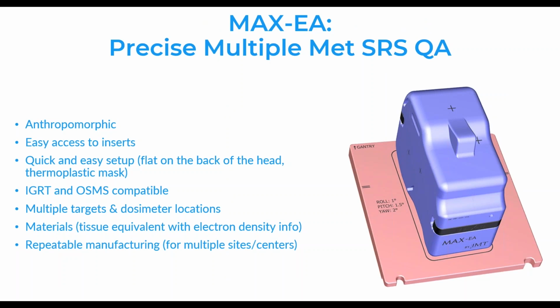So in summary, the Max EA can be used for a precise multiple Met SRS QA. It is anthropomorphic. With the cover, it's very easy to access the insert, and you could quickly set it up because of the machined flat on the back, and it's compatible with OSMS and IGRT systems. It has multiple targets and dosimeter locations. In terms of materials, they are tissue equivalent. We have the electron density information as well. And because of the way we manufacture it, it is repeatable, and so you can use it for multiple sites and centers.